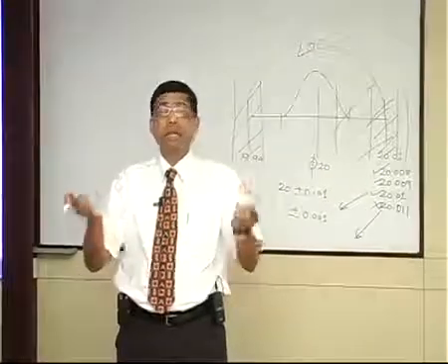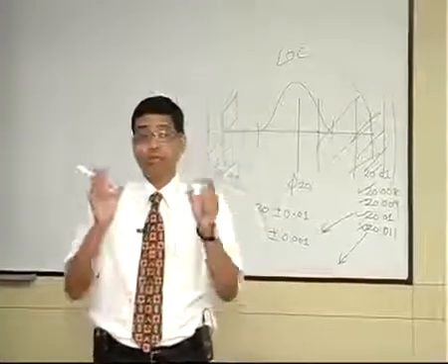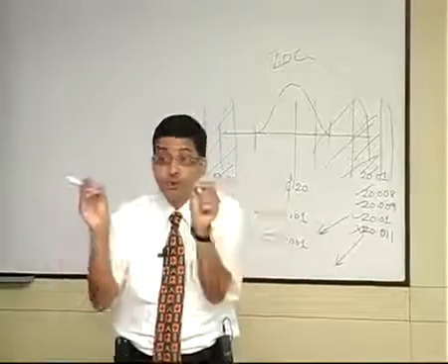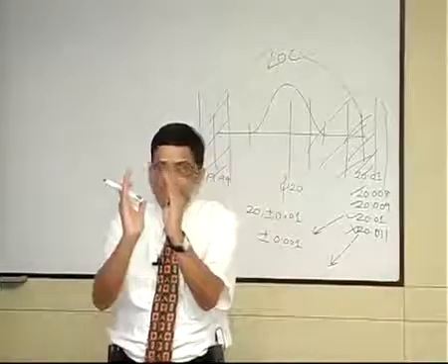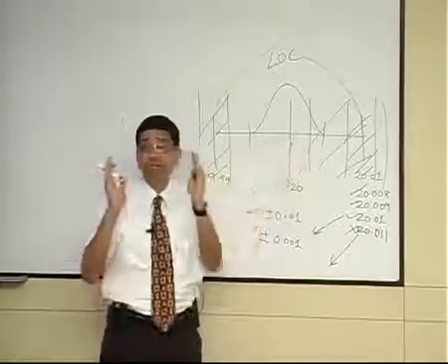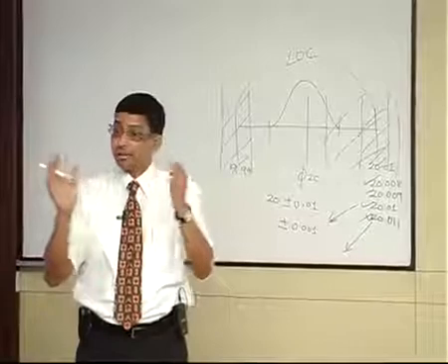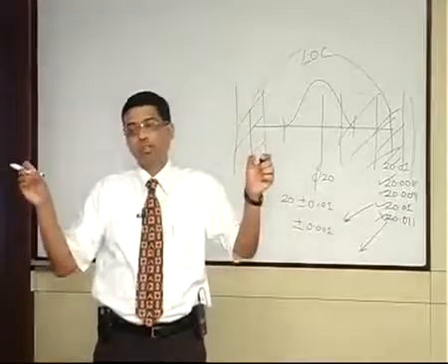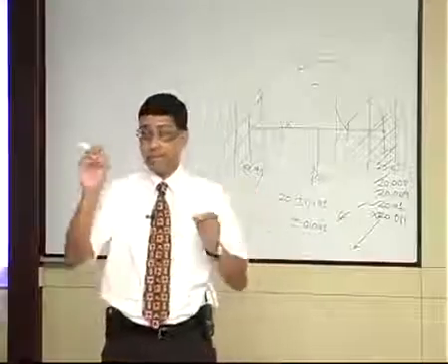So that is why slowly the awareness on uncertainty is increasing. The real best thing is, in any test result, when we do consulting, what we do, we find out what is the uncertainty. And then we ask the production to reduce that tolerance. Plus minus 1, you keep everything inside. And that is what we want. We always want our shop to utilize only 60% of the total tolerance. So it is a good practice to do evaluation of uncertainty, find out, because every result, any result that you get, you must declare uncertainty, always.